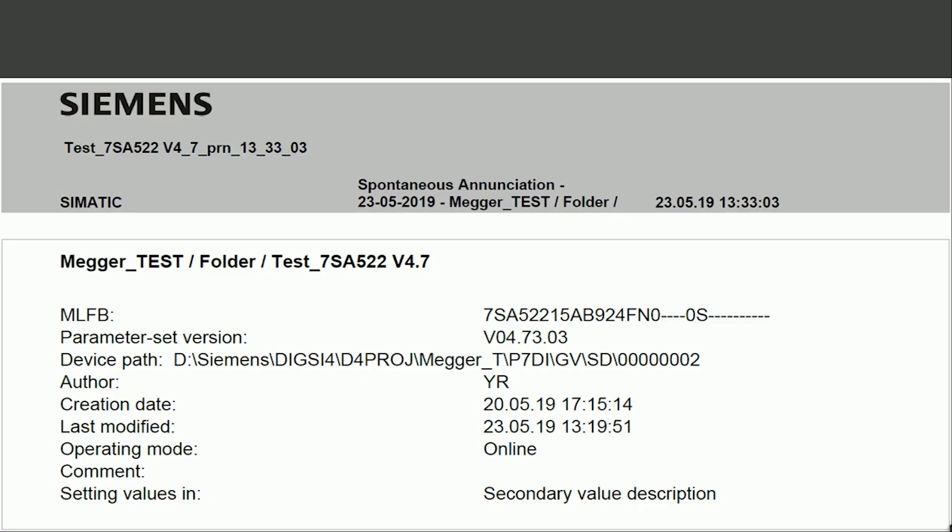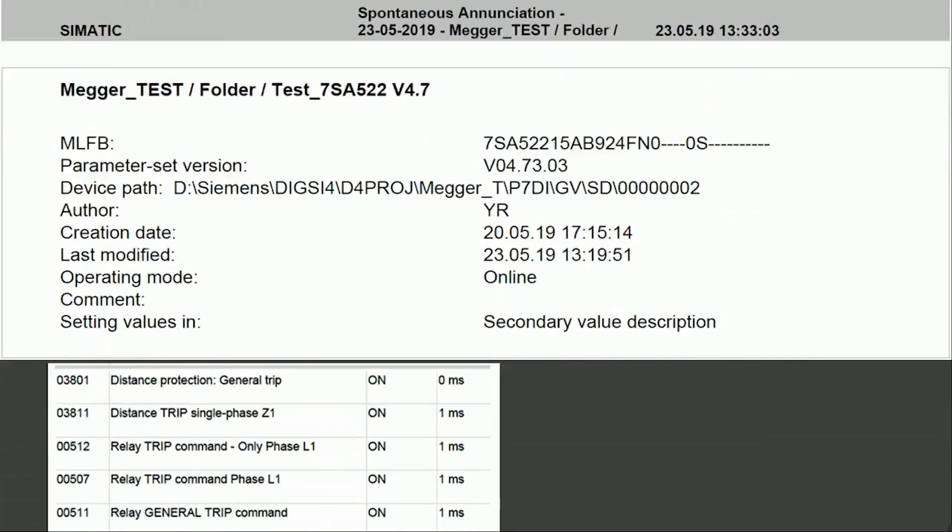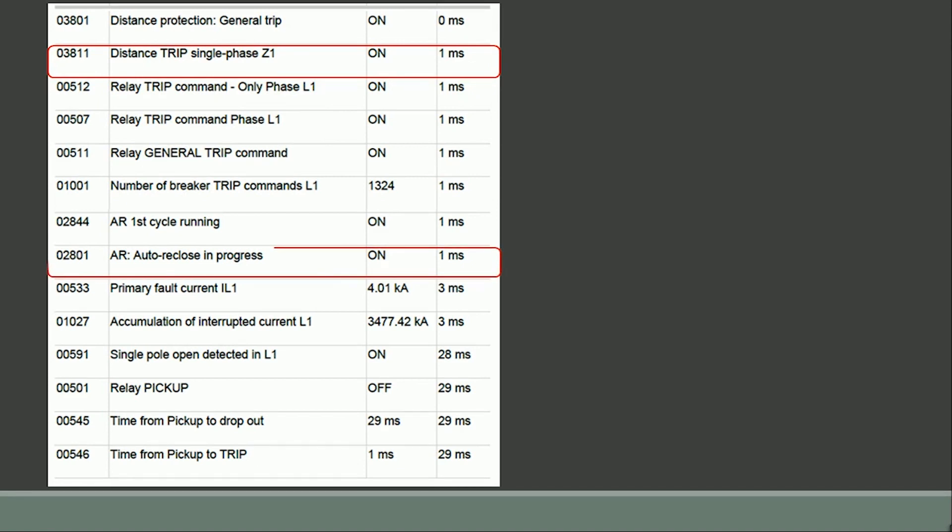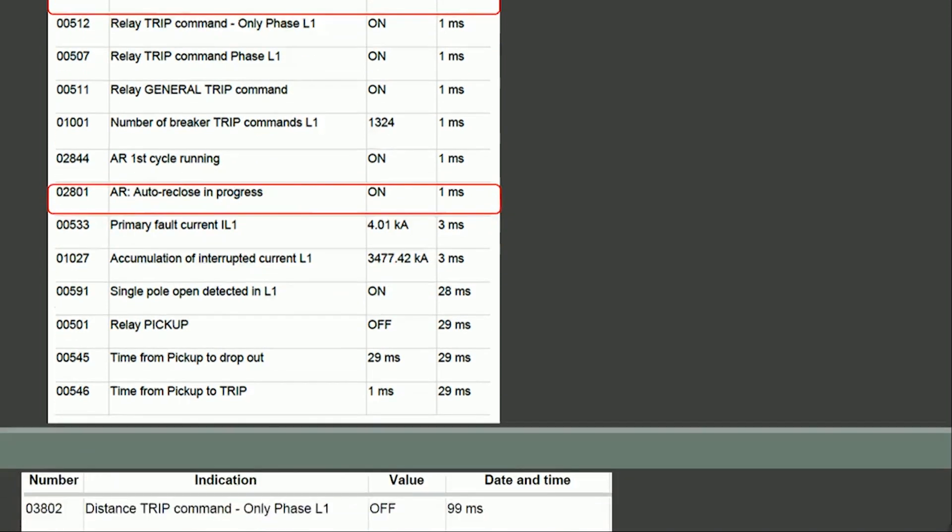Using Siemens DIGSI software the event record is downloaded. The spontaneous event list shows the sequence of auto recloser function. Parameter number 03811 shows the tripping of the relay in zone 1. Further down we can find parameter number 02801 which confirms auto recloser in progress.